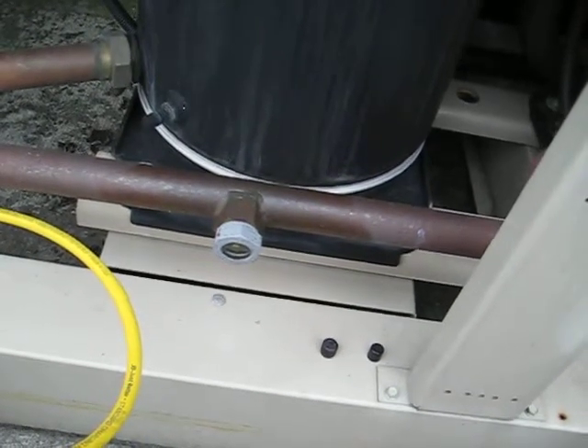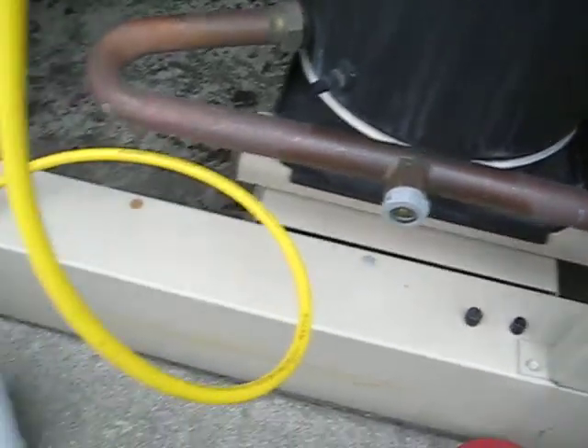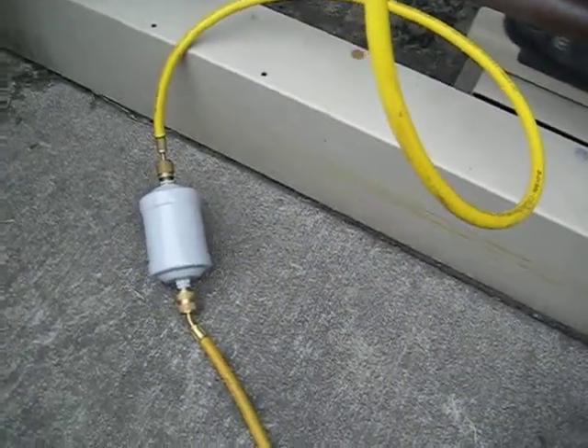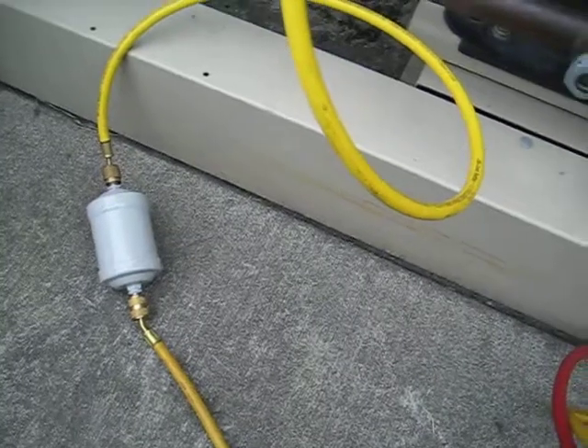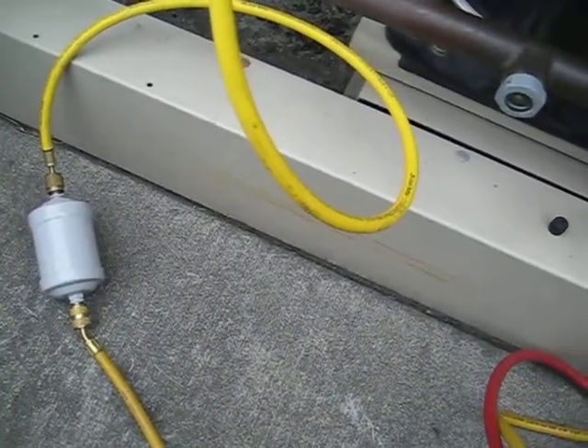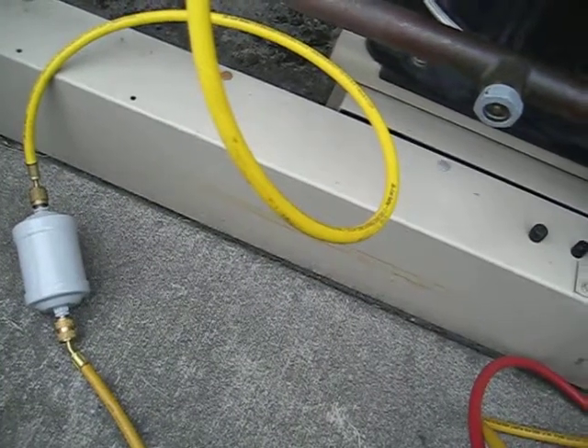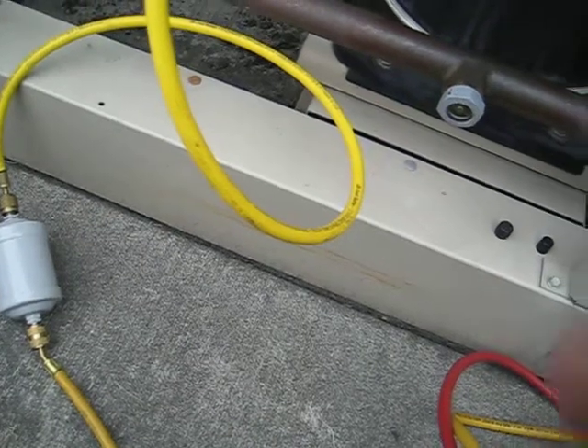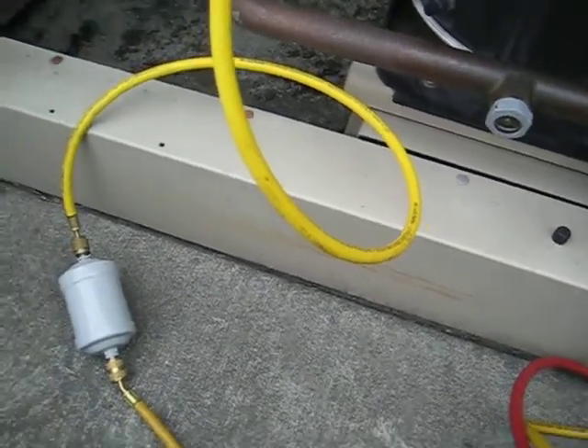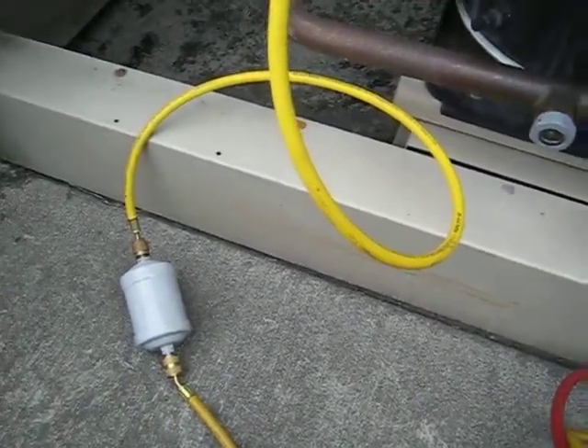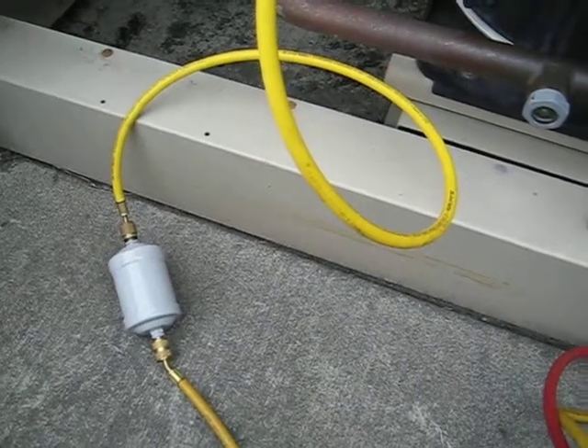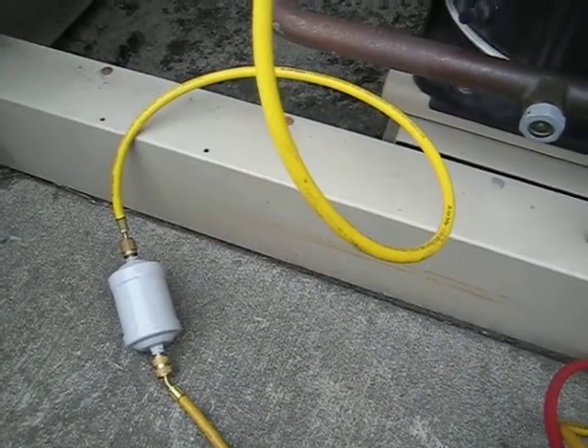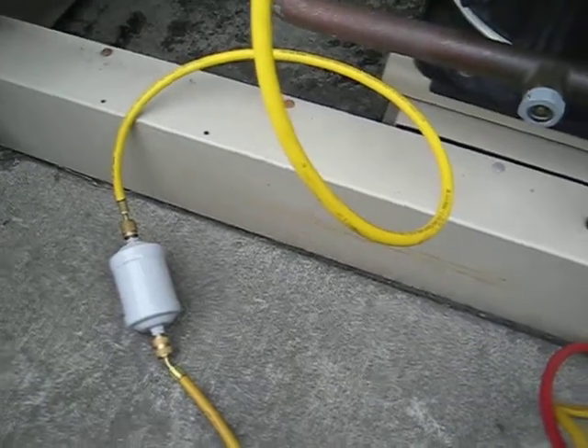And yeah, I use that inline dryer right there too. Then once I put the vacuum pump on this, I'm hoping to get all the refrigerant out of this circuit today. I can put the vacuum pump on there and let it run on Saturday and Sunday. The warmer day, if it's a 90-degree day, that's perfect for evacuating. Hot weather is always better for evacuating. And these hold 130 pounds each. Each circuit holds 130 pounds of R410A.